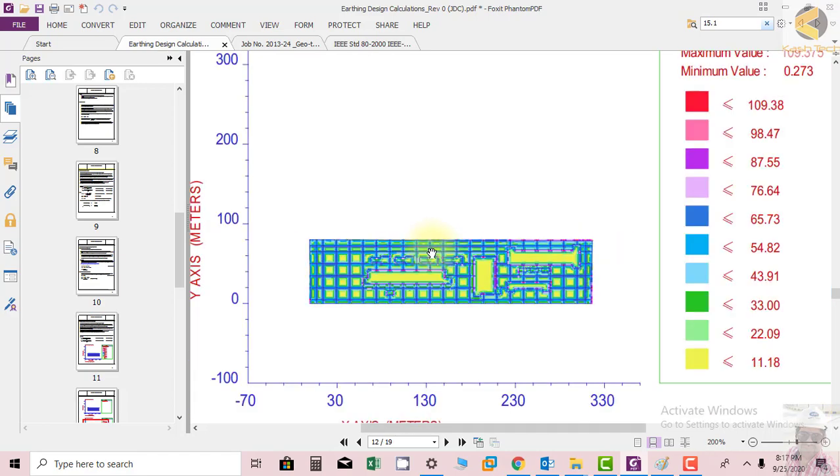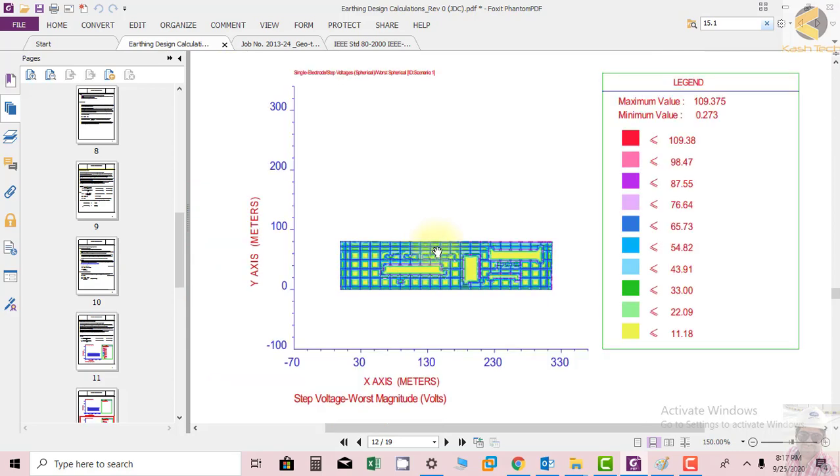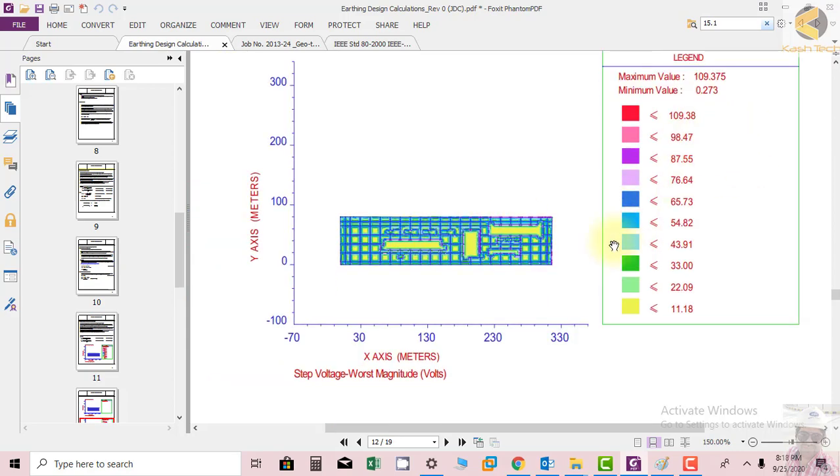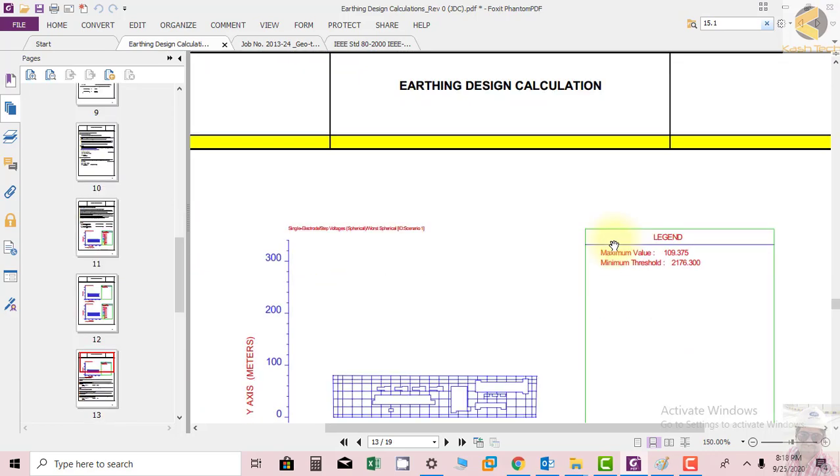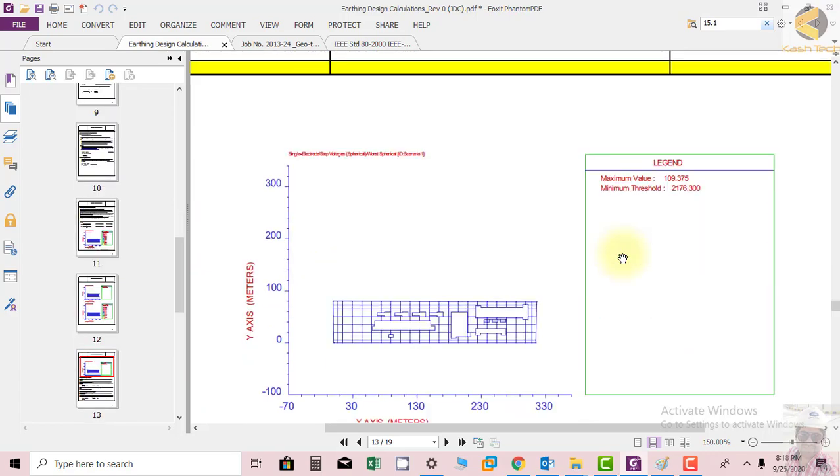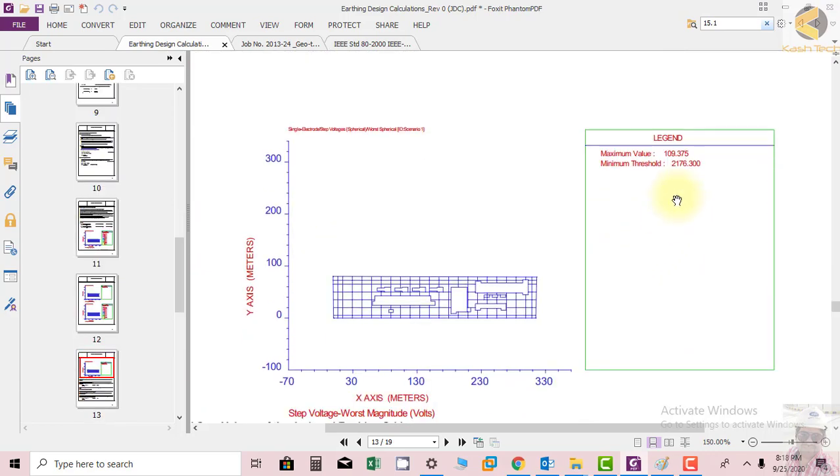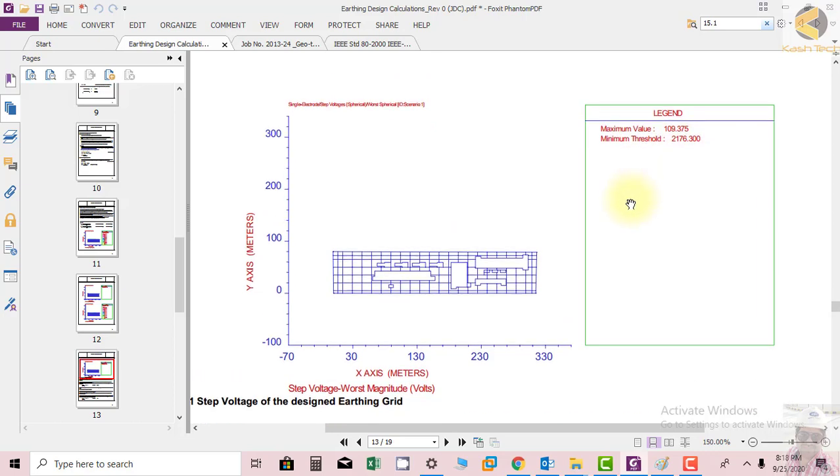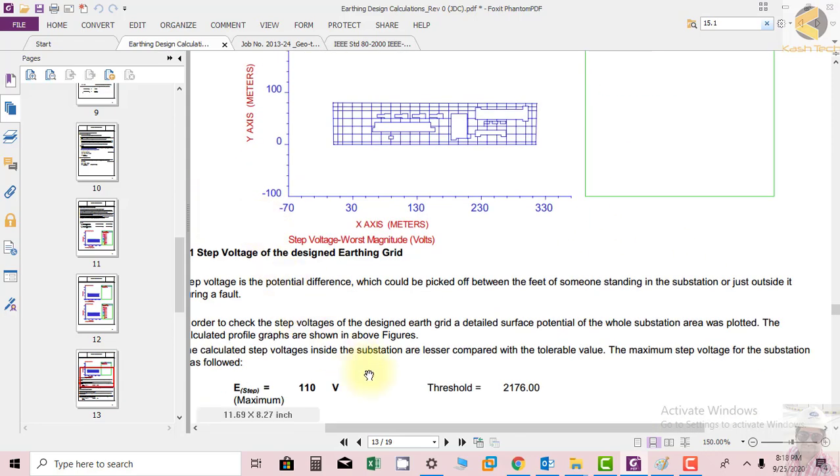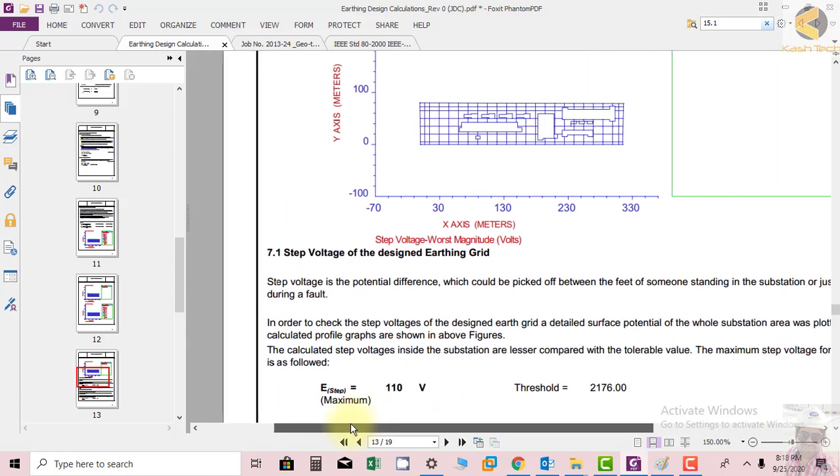Maximum step voltages are 109.38 whereas allowable voltages are, you can see here they have shown, 2176, almost 2 kV. So allowable is 2 kV whereas we are getting 109 which is really below the limit. This is coming from the software so we can say that this is quite okay.